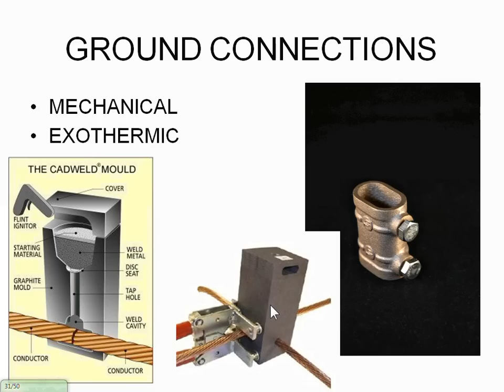We also bond the water, gas, and electric as it comes into the building. The reason for that is you need to equalize the potential. Even if this cable and a 10-foot ground rod is a decent conductor, what happens is it might flash to the water pipe, because the water pipe is a million miles long and actually might be a little bit better conductor. So what we do is equalize the potential so when lightning hits, it dissipates evenly.